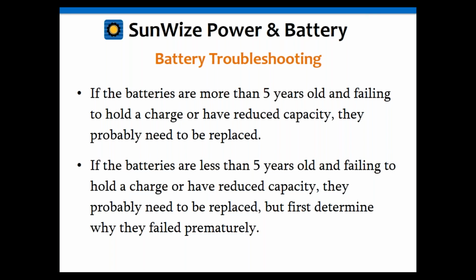If it's less than 5 years and you have a failed battery, if you find you're having issues, it's got reduced capacity, failing to hold the charge, before you put new batteries in and damage a new set of batteries, you might want to find out why those batteries failed prematurely. It could be something as simple as somebody used the wrong setting on the charge controller. Maybe they had too low a voltage setting or too high a voltage setting for regulation. Could be something that simple, maybe something bigger than that.